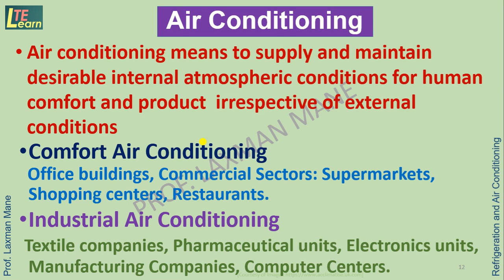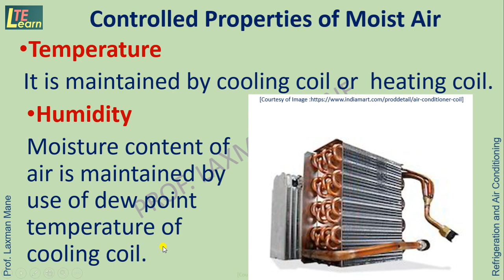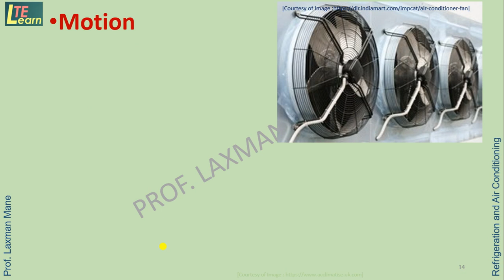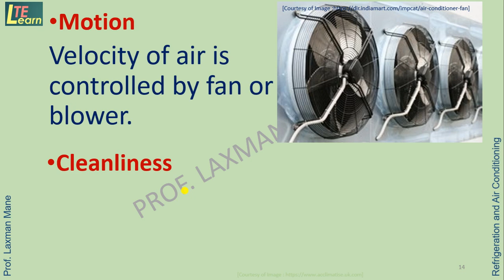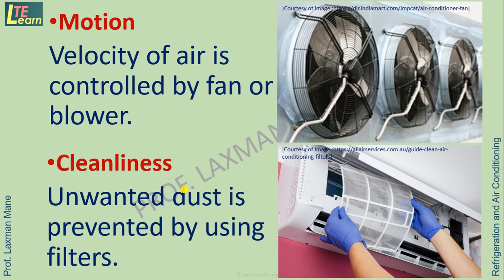In air conditioning, mainly four properties of moist air are controlled simultaneously: temperature, which is maintained by using cooling coil or heating coil; humidity, meaning moisture content of air, is maintained by use of dew point temperature of cooling coil; motion of the air, meaning velocity, is controlled by use of fan or blower in the air handling unit; cleanliness, meaning purity of air. Here unwanted dust is prevented by using filters.